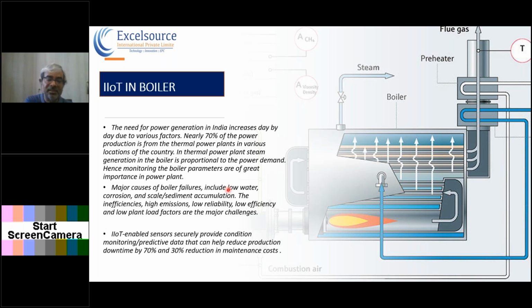This can also help us optimize the power consumption, because lower fouling will help us optimize the ID fan power consumption, and we can even plot a curve of ID fan consumption based on the flue gas analysis. We can install a flue gas analyzer, and these analyzers can help us identify the extra air going inside and how we can avoid that, and get the ID fan to operate at rated or below rated RPM, and then we save energy. So in a nutshell, we will be able to optimize the cost of steam production, and this can go as high as a 30% reduction in the maintenance cost.